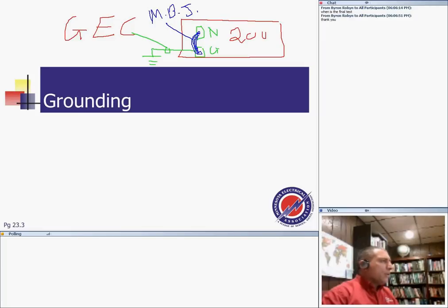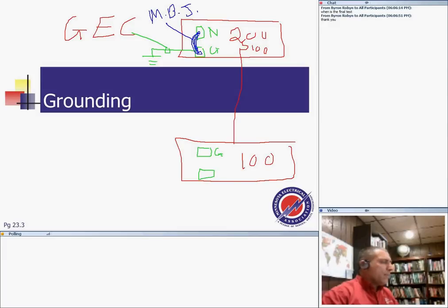And the third one, so if you don't know this, you're confused. Suppose I have a 100 amp panel here, and suppose this 100 amp panel is fed from this 200 amp panel, right? I can do that, right? With this 100 amp panel, here's my ground and here's my neutral, and I never bond them in the second panel, but I need an equipment grounding conductor, and that conductor comes over here. This conductor is called the equipment grounding conductor, basically the ground wire.